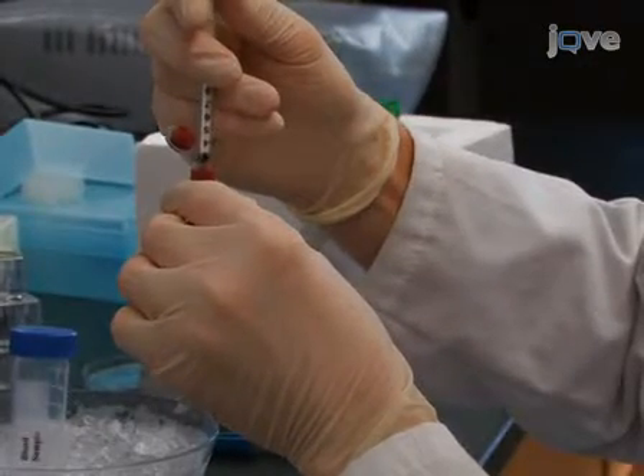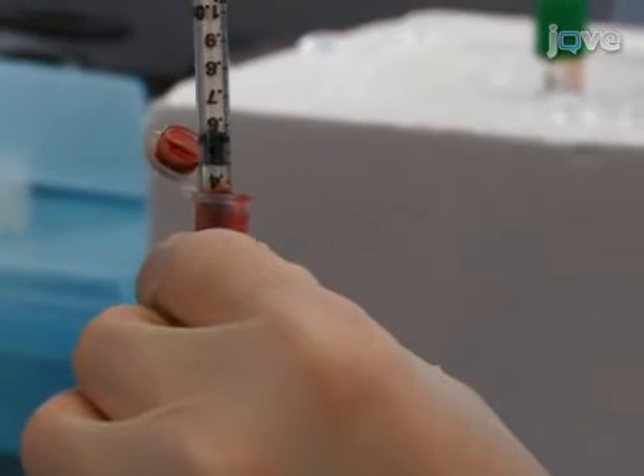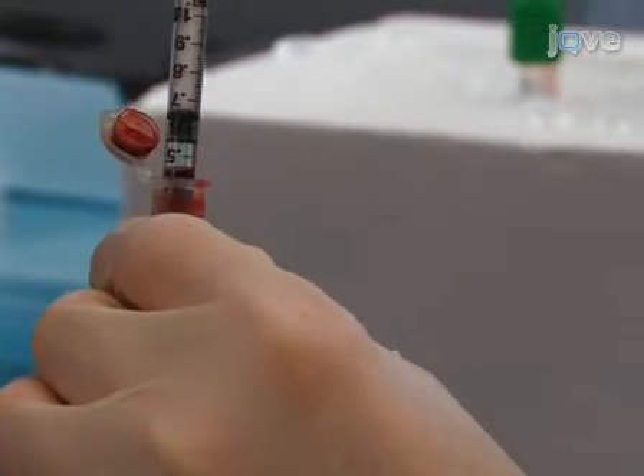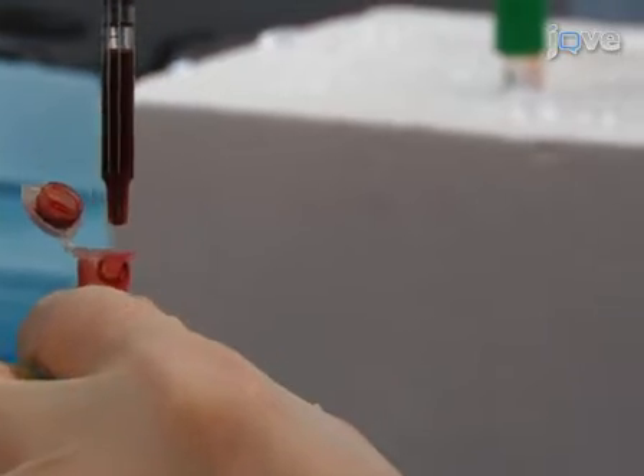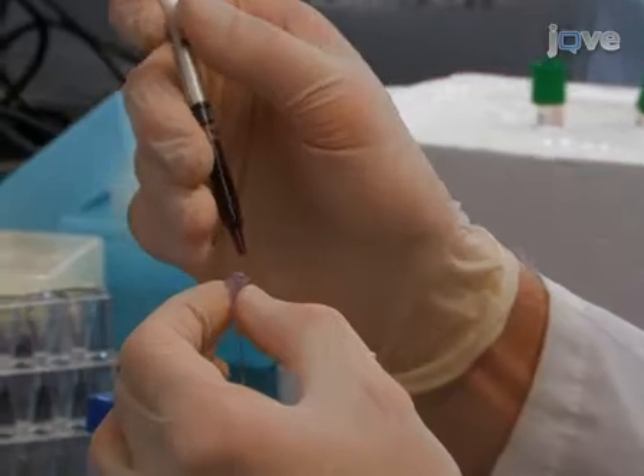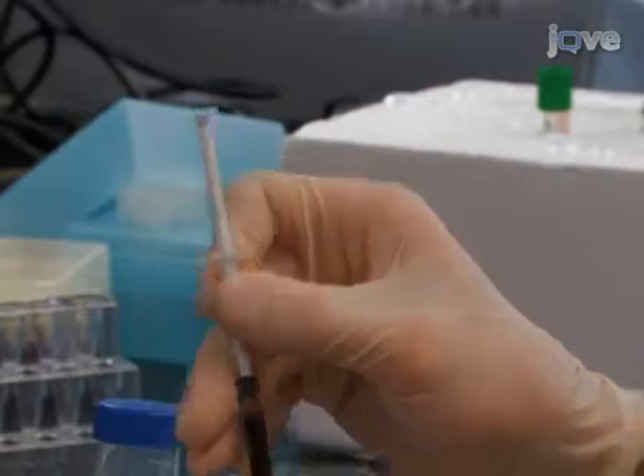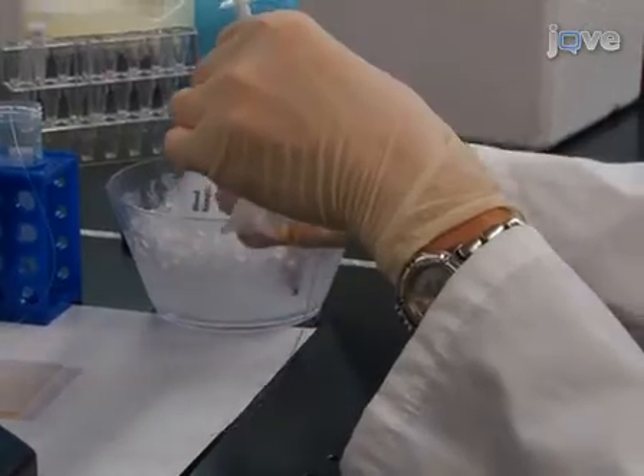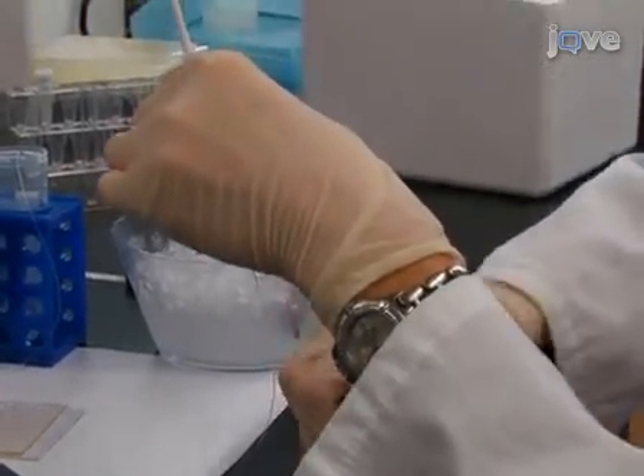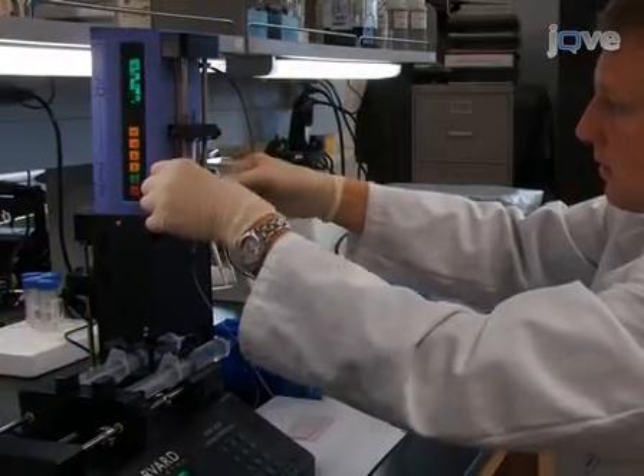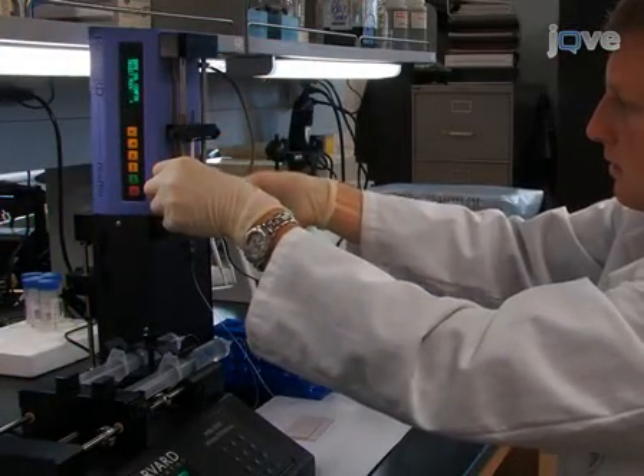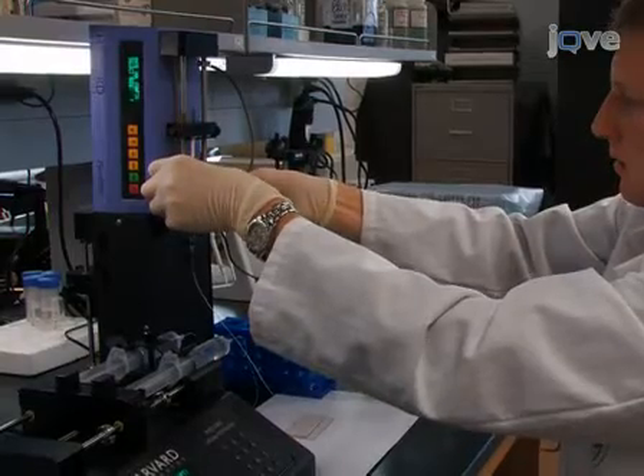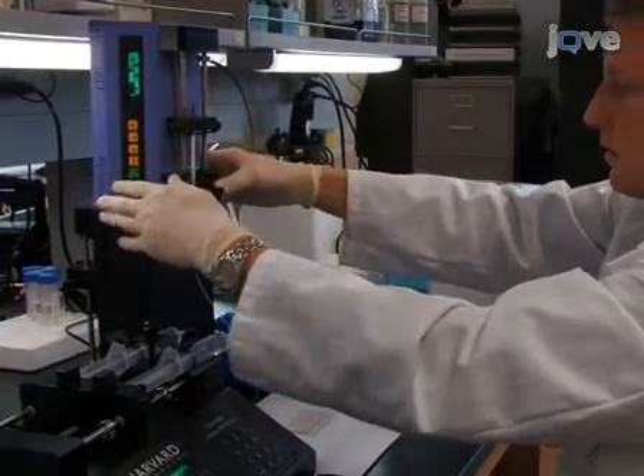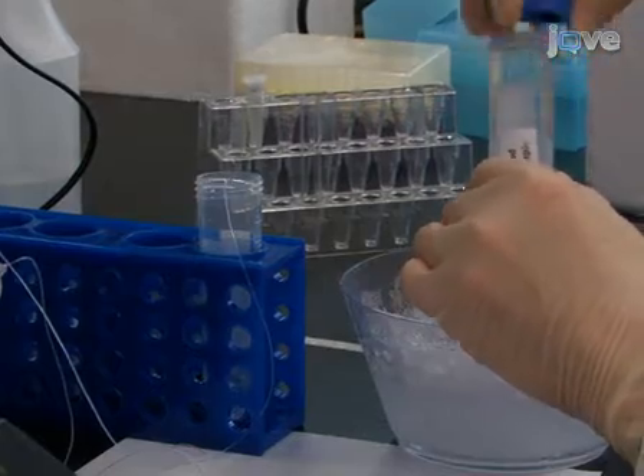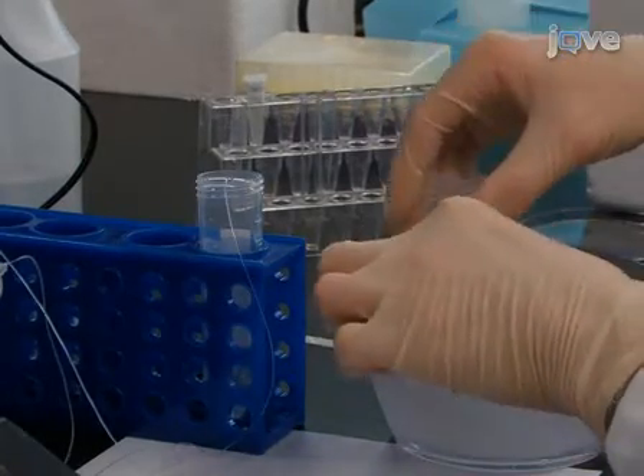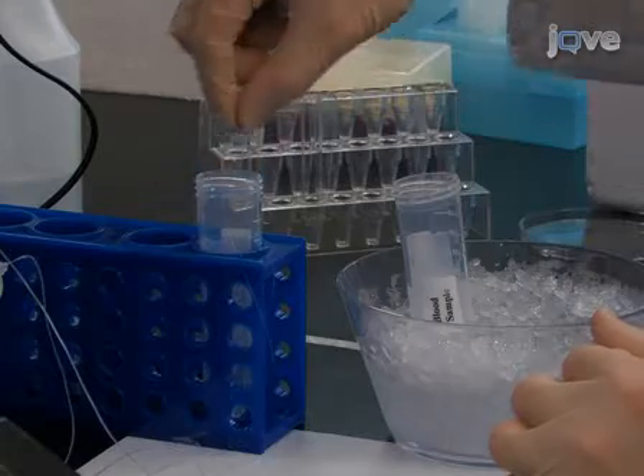Then fill the syringe with 0.5 ml of blood. Keep the syringe vertical while filling to avoid mixing of the PBS with the blood. Next, connect the syringe containing the blood back to inlet 1. Wipe away any excess fluid and mount the syringe vertically on the small Harvard syringe pump. Be careful not to push the blood through the tubing into the device. Remove the outlet tubing from the waste tube and place it in a clean 50 ml centrifuge tube sitting in an ice bucket.